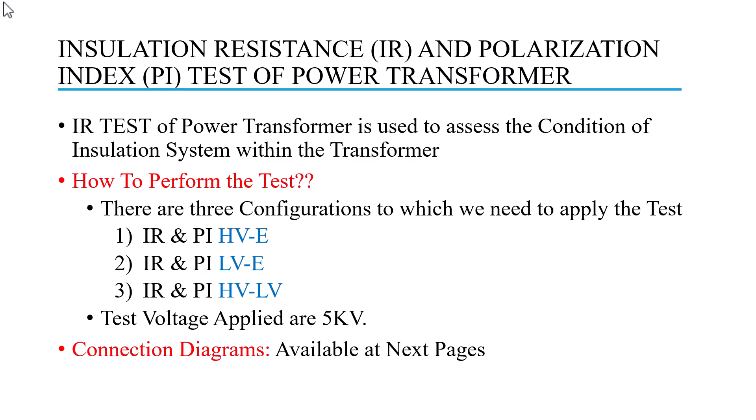The insulation resistance test of a power transformer is used to assess the condition of the insulation system within the transformer. As you know, in the transformer we have windings and a core. The windings are separated from each other, from the core, and from ground. So windings have insulation properties, and to judge these insulation properties we need to do the IR test.